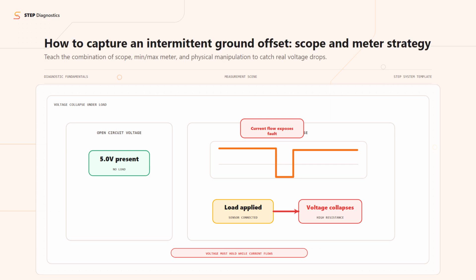To catch an intermittent offset, use a scope or a min-max recording meter directly across the sensor ground and battery ground, ideally with the circuit loaded and while applying heat, vibration, or movement. Scope reveals fast drops that scan data misses. A meter with min-max may also catch events if the timescale fits.